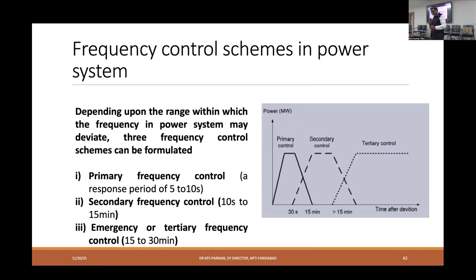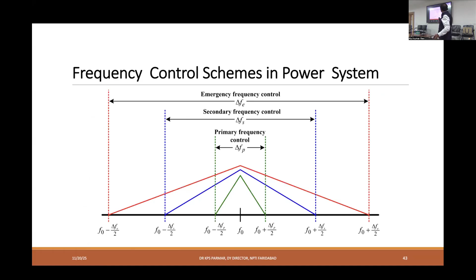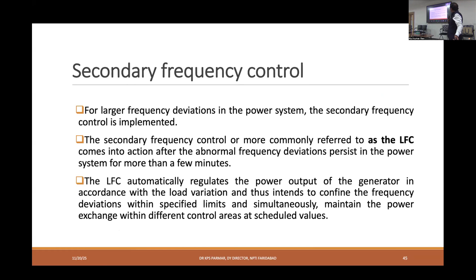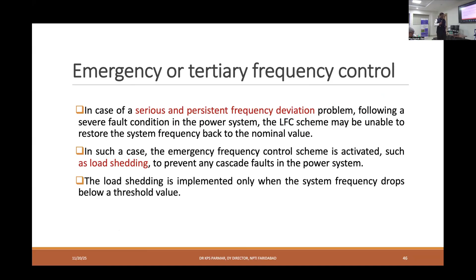In the emergency, it means we have other options like going for load shedding also. So this is the graph: primary I have told you, secondary also I have told you, so emergency or tertiary is the load shedding part. Suppose there is some protection issue, some malfunctioning of relays, and loss of generation or loss of load for a longer period at a larger scale, then we go for this tertiary control.